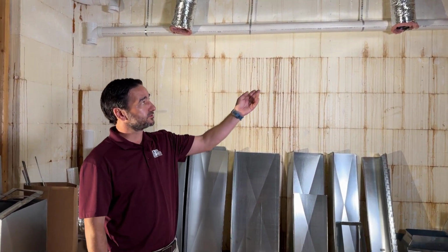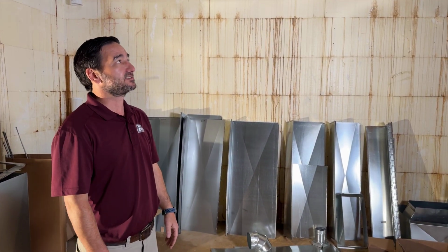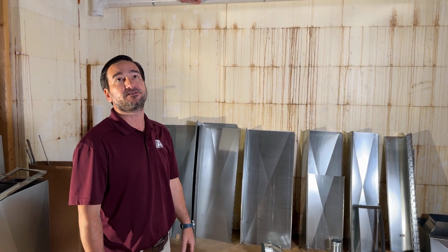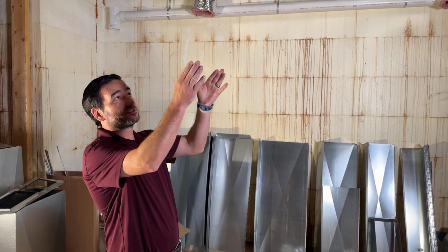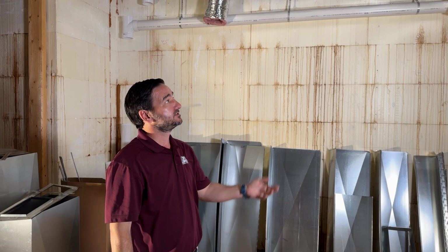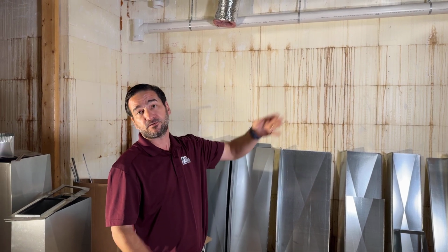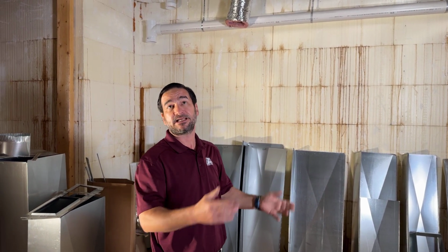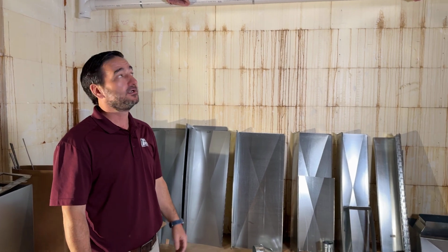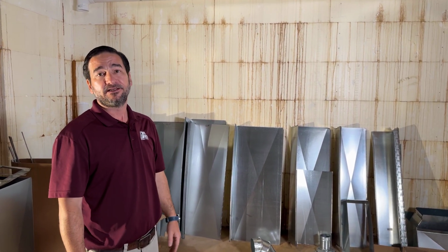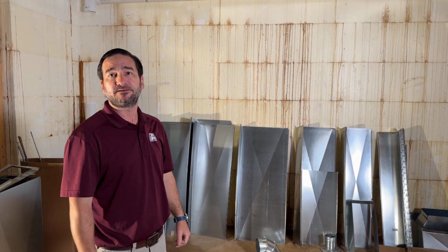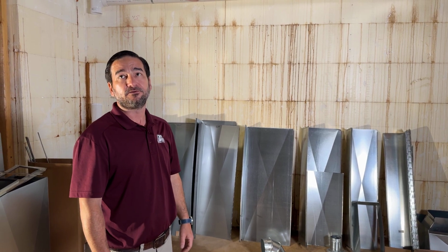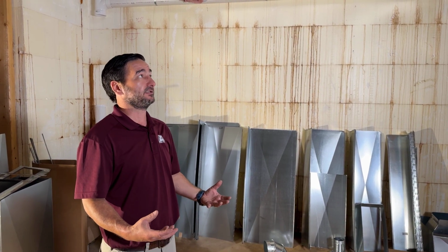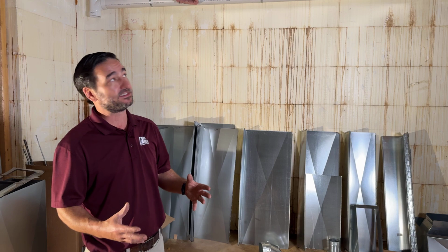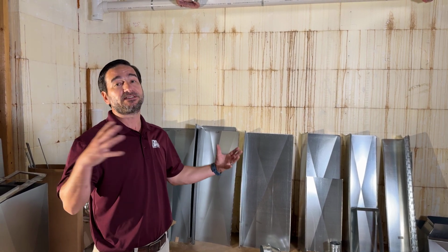Correct. So a normal square-backed elbow, I believe, is somewhere around 30 equivalent feet of duct. So each one of these sections of duct up here is 4 foot long. So just putting a 90-degree turn with no turning vanes is basically like adding 30 feet of that straight duct. When we add the turning vanes to that, it actually reduces the friction rate down to about 15 equivalent feet. So if we didn't use these, we would have to increase the size of the ductwork to overcome the friction.